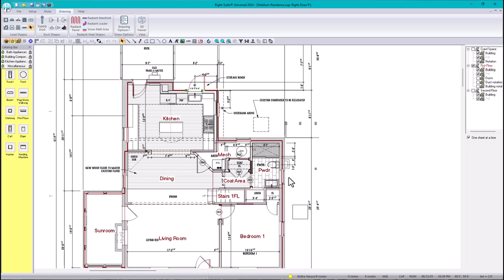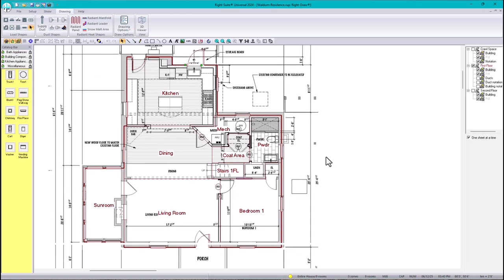If you're a contractor and you have a homeowner that wants a heat load calculation, you can always tell him, hey, can you take an approximate number of what the dimensions of the windows are, or even take a picture. Or number 3, even in the drawings that the architect provided, there is a scale. By the scale, you can know what the windows are, okay? So basically, in the drawings, you have the floor plan and you have the elevations. So you have to check the elevations.